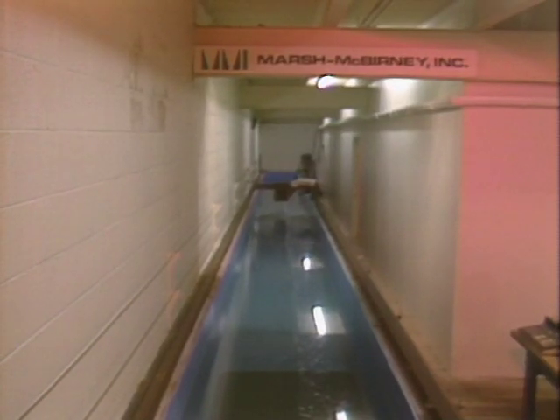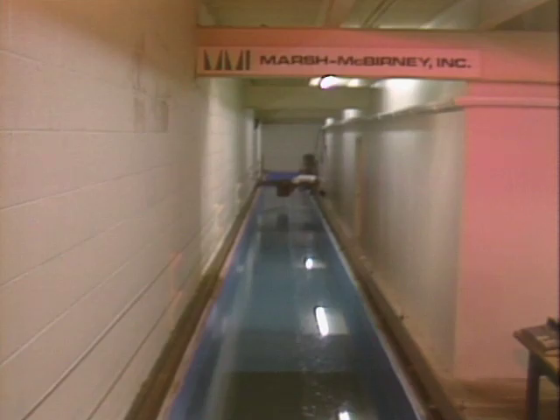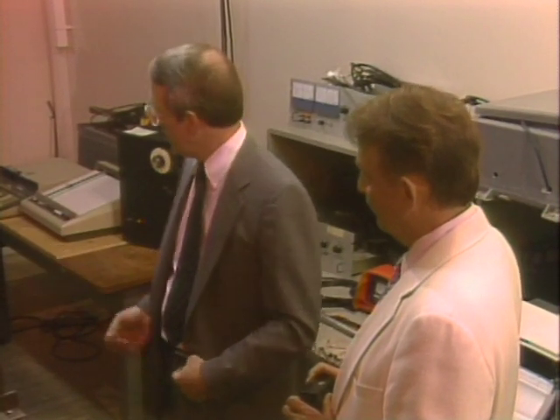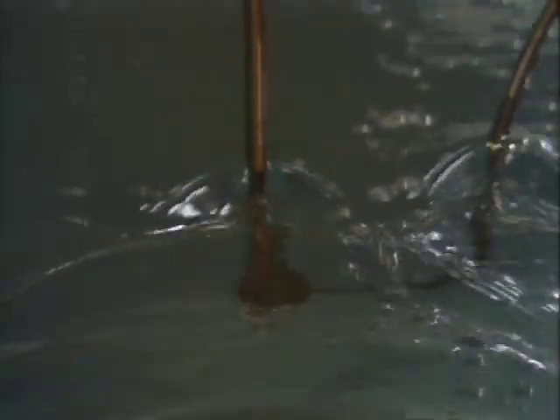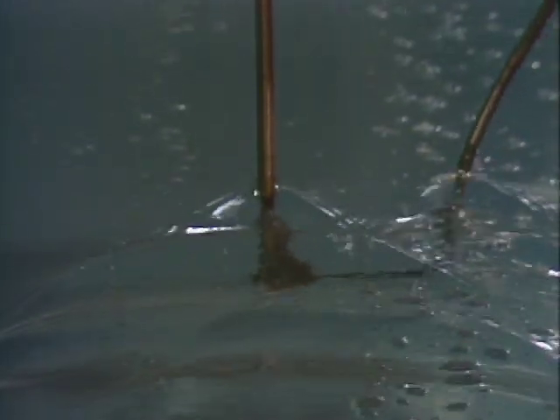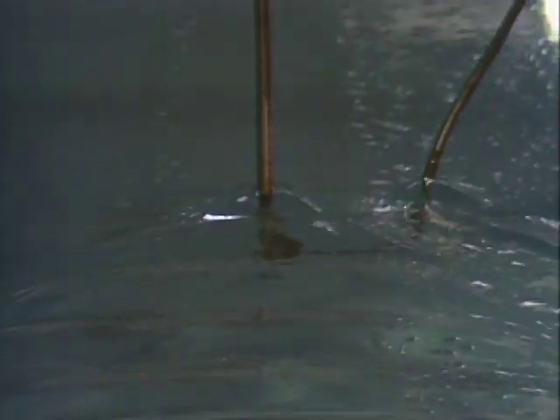Towing carriages like this one are the preferred method of calibration at government installations and major universities involved with sensor calibration. At Marsh McBirney, sensors can be tow calibrated to achieve an accuracy of one quarter percent.